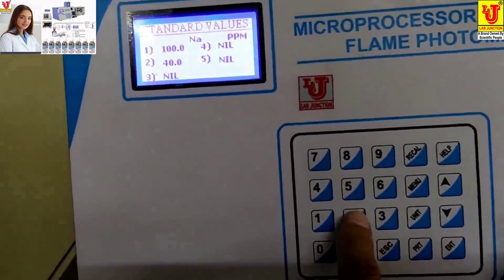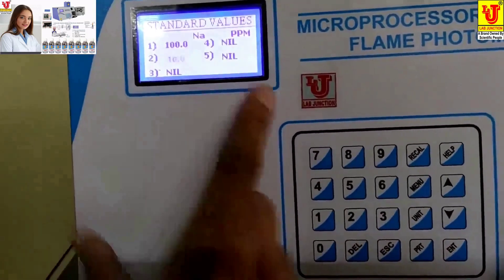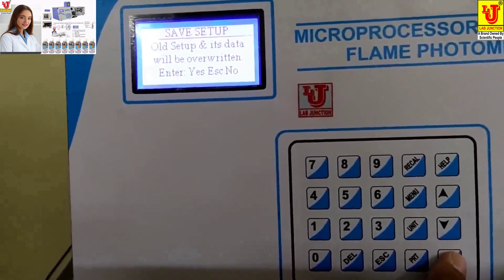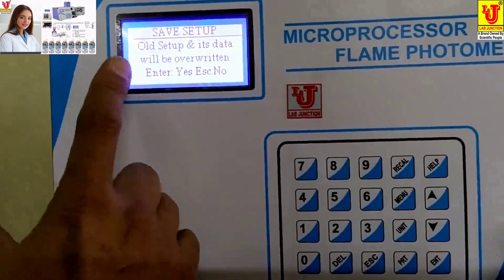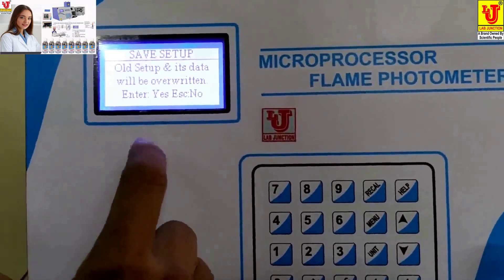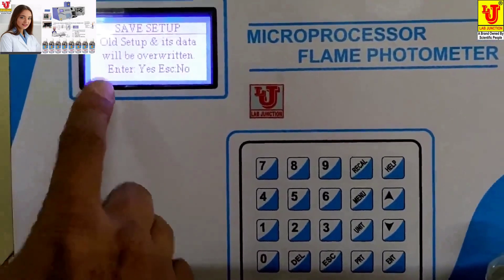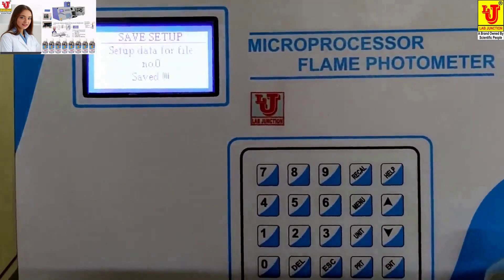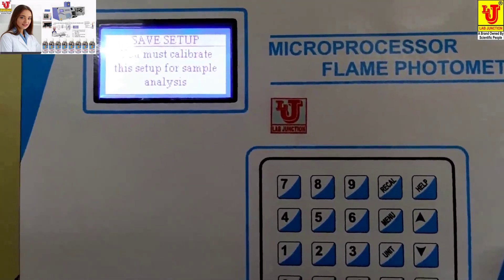Setting standard 2 as 40. Press Enter. It says old setup and its data will be overwritten. If you press Yes it overwrites; if you press Escape, previous data remains. I press Yes. Setup data for file number zero is set. Now go to Calibrate — press key number 3. It automatically takes zero.